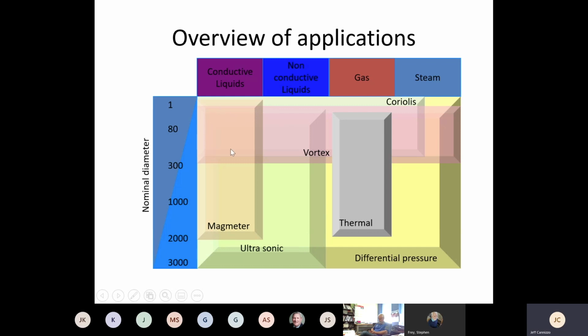Vortex meters fill a nice niche across all categories. They can actually go up fairly high temperature, about 800 degrees, so they can handle a lot of superheated steam. They're meant for gases and steam, typically clean. They can handle non-conductive liquids, so vortex meters a nice choice in DI water, areas like that. And they can obviously handle conductive liquids. What they can't handle is high viscosity. And we talk about high viscosity in turndown. Even viscosities of 5 centipoise or greater will start to affect the vortex meter's lower flow capabilities, low range capabilities. But generally anything over 20 centipoise, we will not even consider a vortex meter.